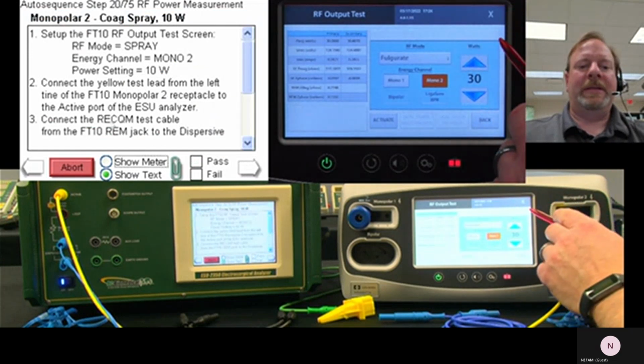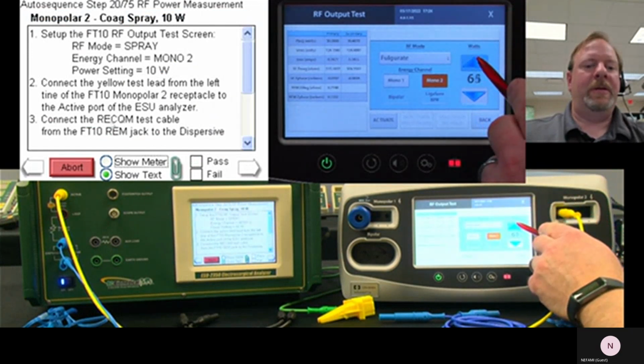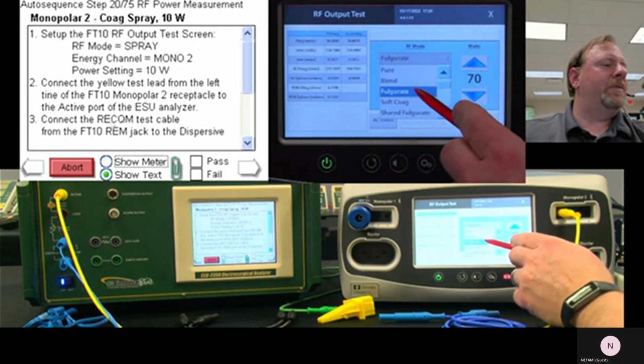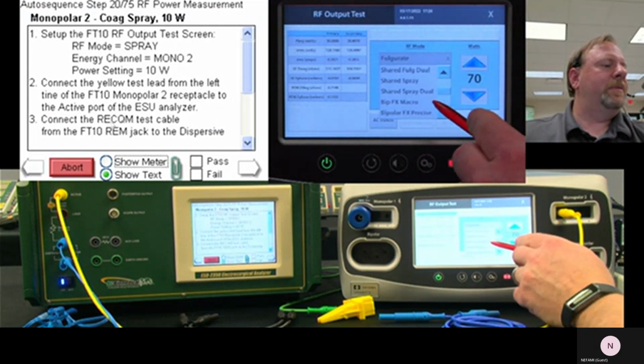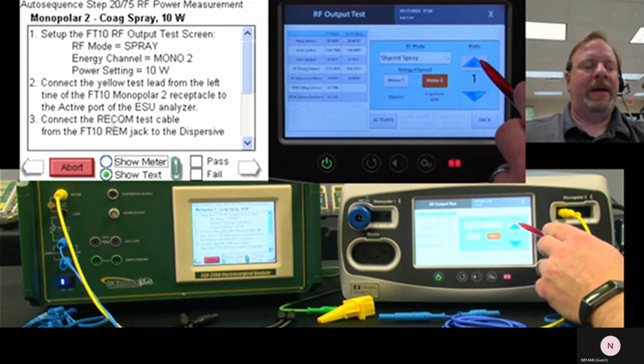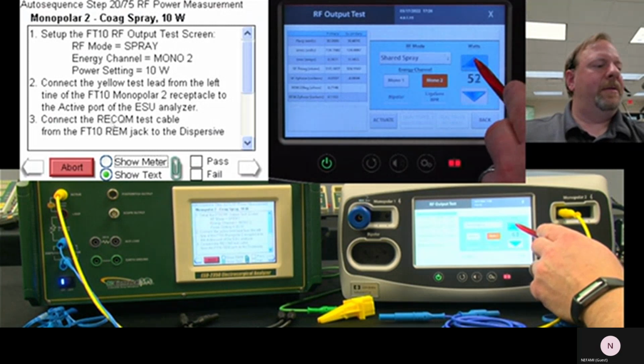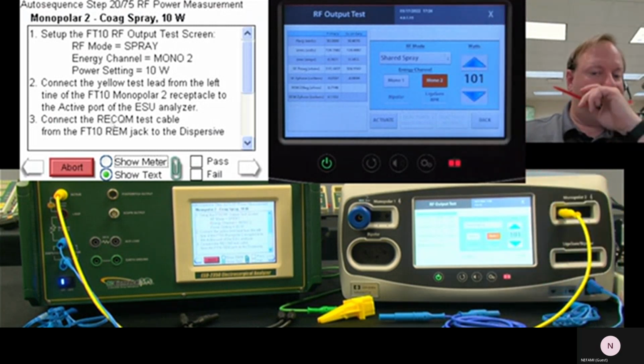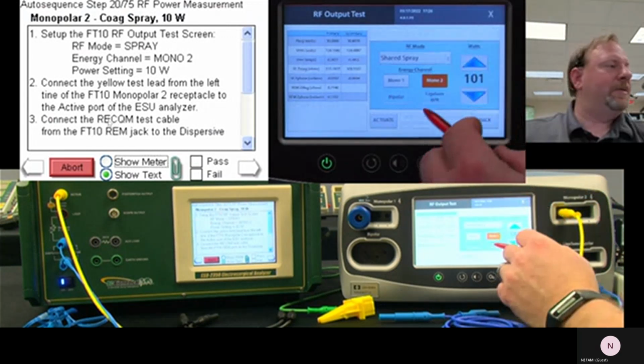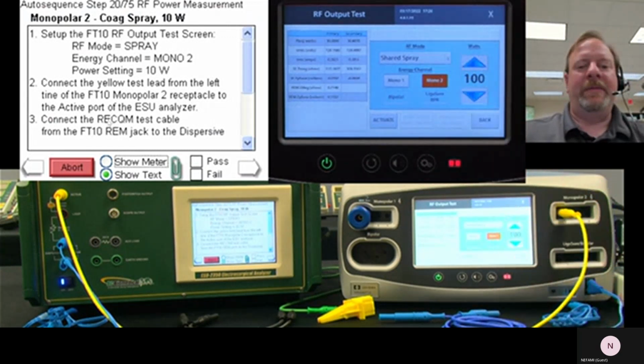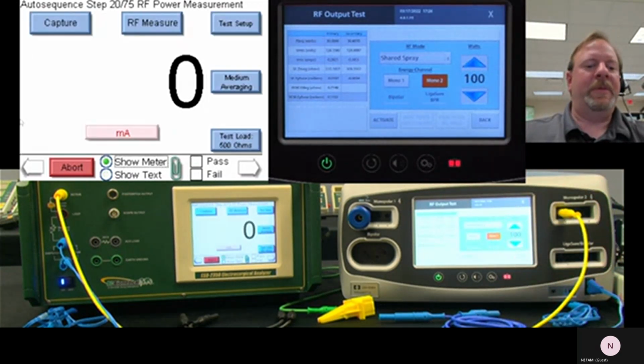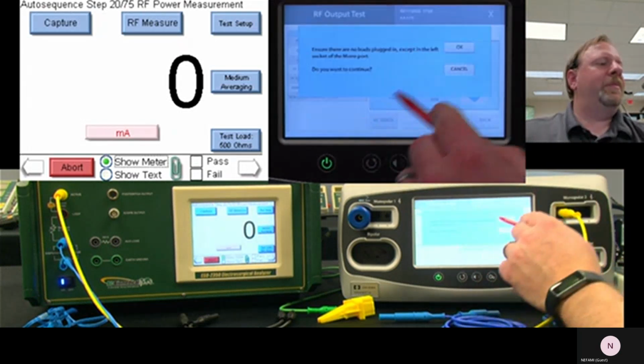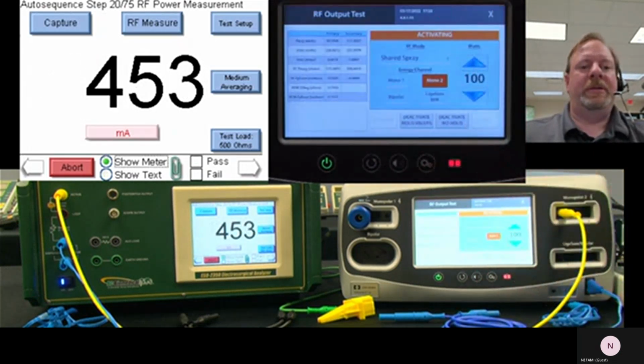Now I'm going to try and set this one intentionally wrong. Let's just do this. We'll go to spray. What happens if I do this wrong here? Monopolar 2, it says 10 watts. Yep, I set it to 10, right? So then I go in here, show meter. Sure, activate the output. Thank you very much. I hit capture. Oh, that's a fail.